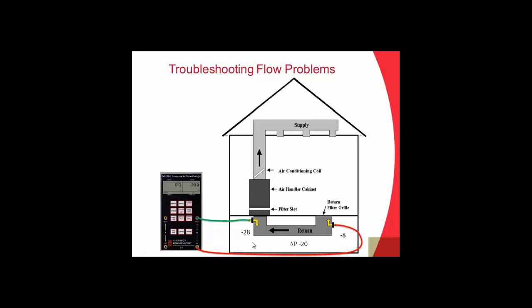So the difference between those two is -20 pascals. So we've switched our tubing connections here now. So we're measuring the difference between the location just before the furnace filter and the pressure over on the side here. The difference between those two is 20 pascals. So we have a 20 pascal pressure drop along this section of return. The difference between -28 and -8, the distance between those two numbers is the change in pressure, which is -20. So now we know that we've got some restrictions based on elbows and length of duct.